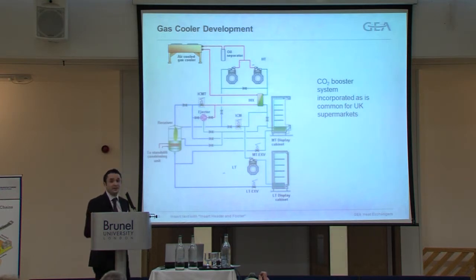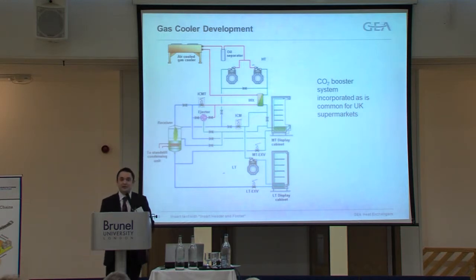Okay, so the first stage of this project, of course, is to have a test facility. This is the test facility at Brunel. You can see the gas cooler at the top there. I won't go into it in too much detail because Danfoss and Frigido will be able to speak about it better than I. But you can see the high temperature and the low temperature compressors separated, and the ICMT valve there, which is used to control the operation of the gas cooler.